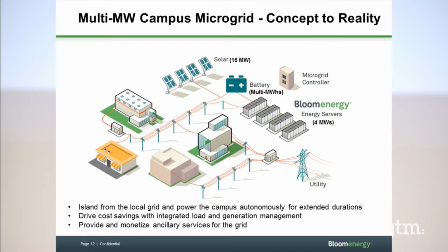We have 4 megawatts of Bloom at this campus, combined with multi-megawatt hours of batteries, and also 16 megawatts of solar. The coolest thing about this architecture is that it's a large-scale, almost medium-voltage utility-scale solution, where the batteries and the Bloom solution sit on a large-scale DC bus with a utility-grade inverter, feeding a medium voltage loop for the entire campus.